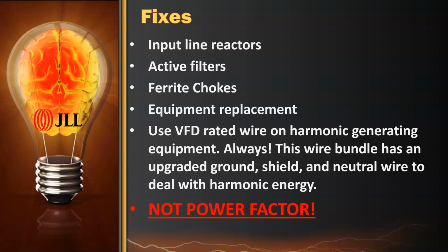You could use an active filter. Active filters are basically like hockey goaltenders. They read the harmonic or transient signal coming in and produce an inverse signal to cancel it out. Input line reactors have a fairly good lifespan, much like a transformer, 15, 20 years. Active filters typically don't have that kind of lifespan. They're usually in the 5 to 7 year range.